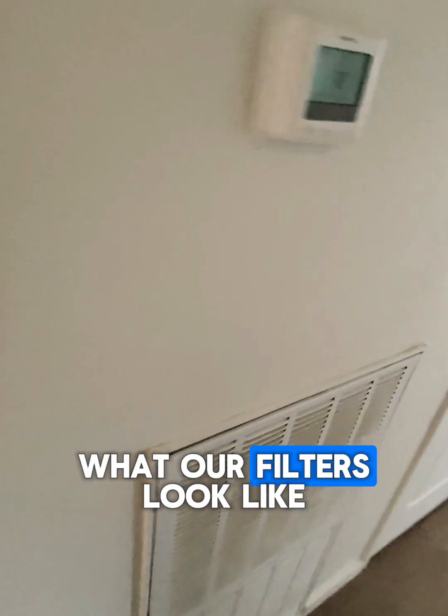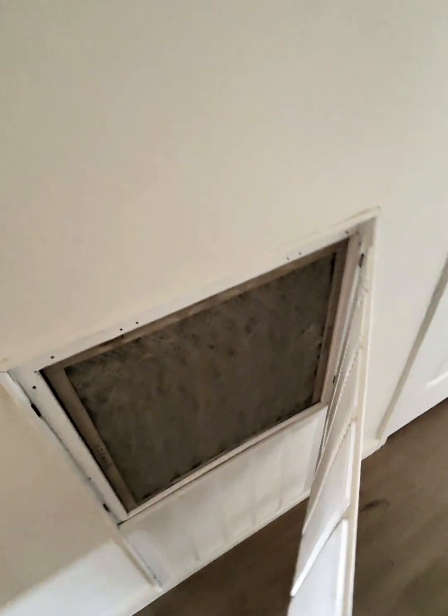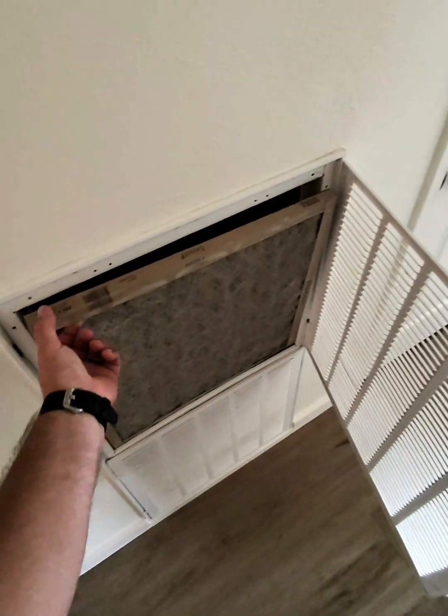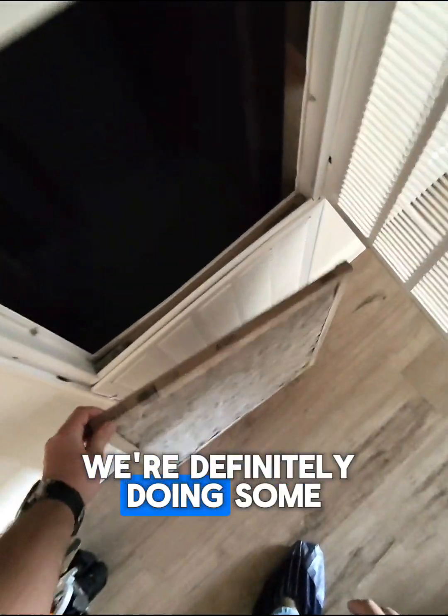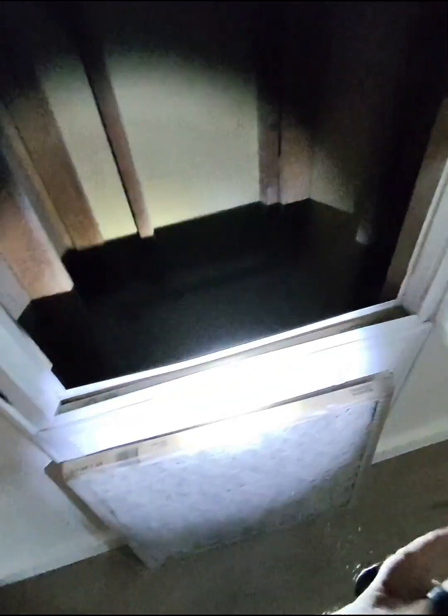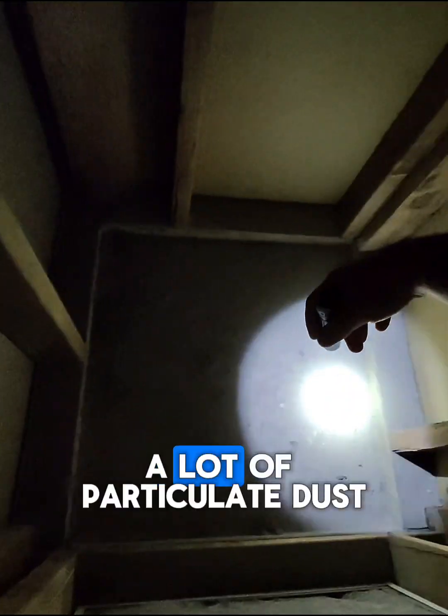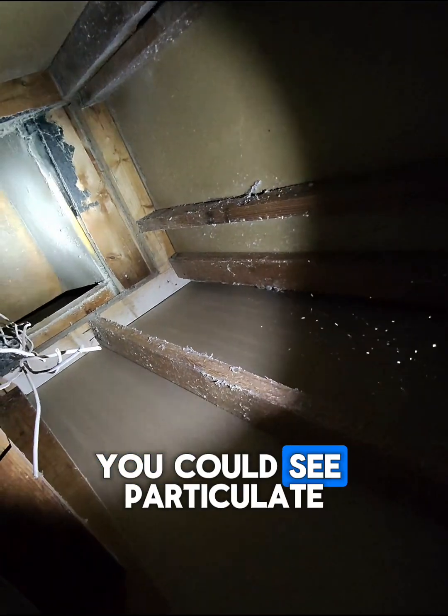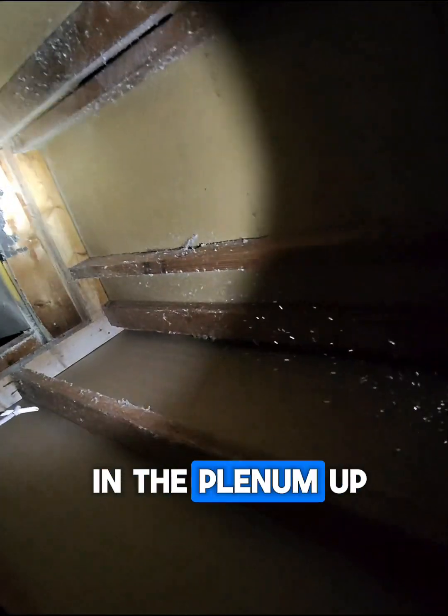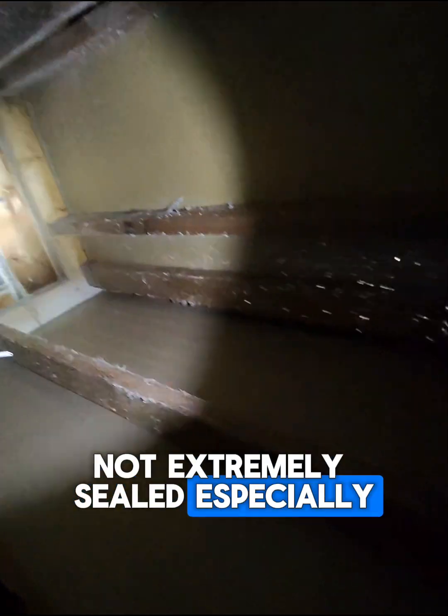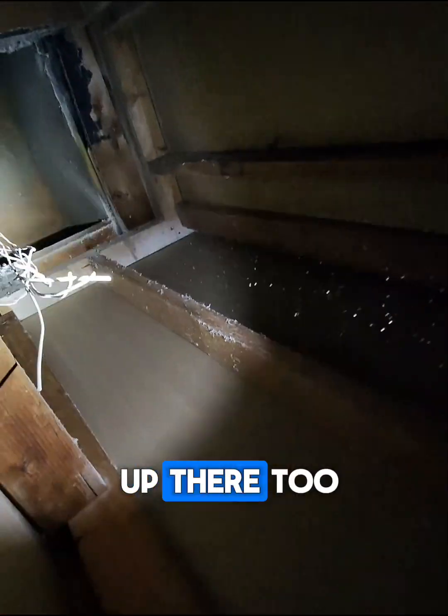Let's go ahead and see what our filters look like. We're definitely doing some painting and stuff. Still got some here in the filter. 20 by 20s, got two of them. A lot of particulate and dust. You can see particulate and dust build up in the plenum up there too. Not extremely sealed, especially around the studs and everything. We'll look at it up there too.